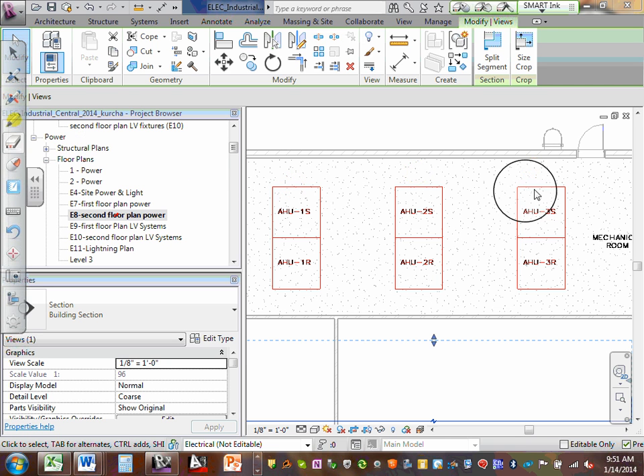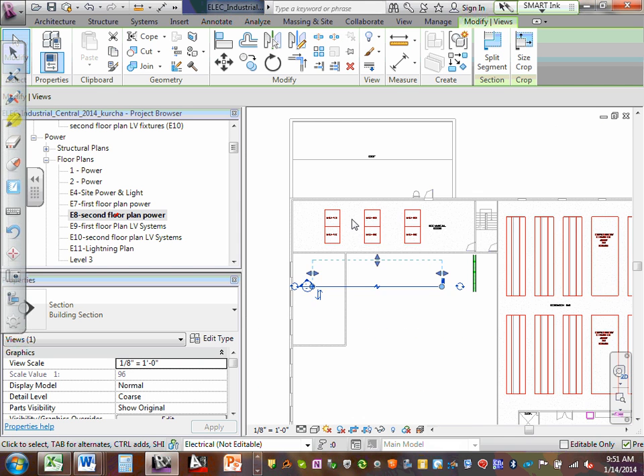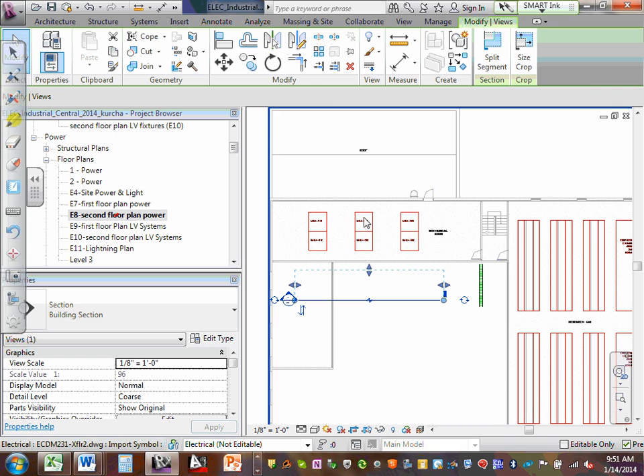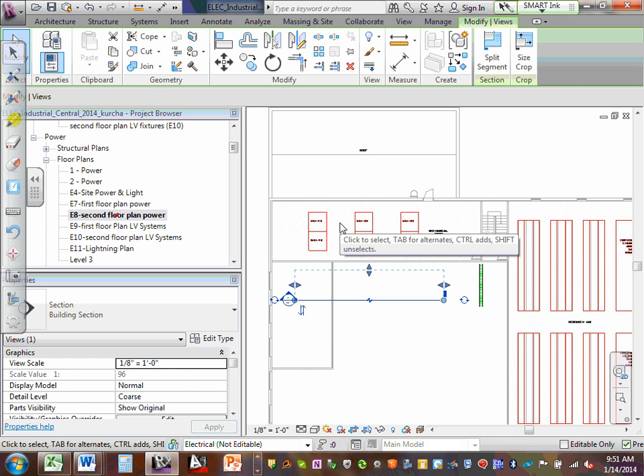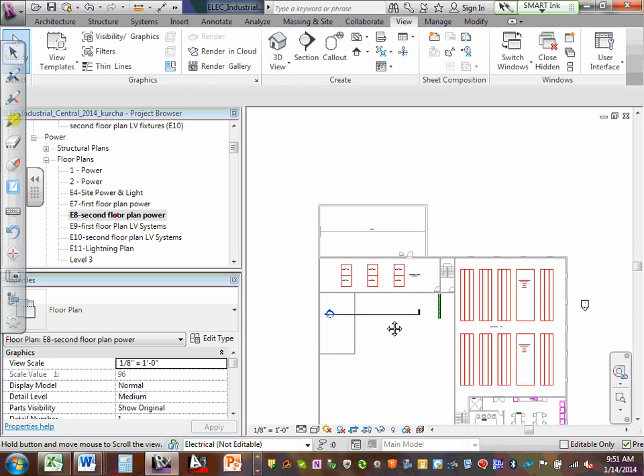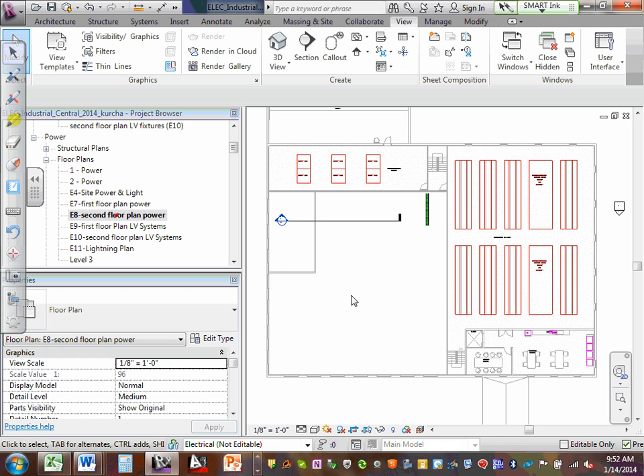So the operation of a fire alarm system is to monitor fire events and then be monitored off-site by a listed central station, which calls the fire department and or building owner, depending on the type of signal that's being received. Smoke detectors are not required in this building at all by the code. Now, I believe the criteria says what?